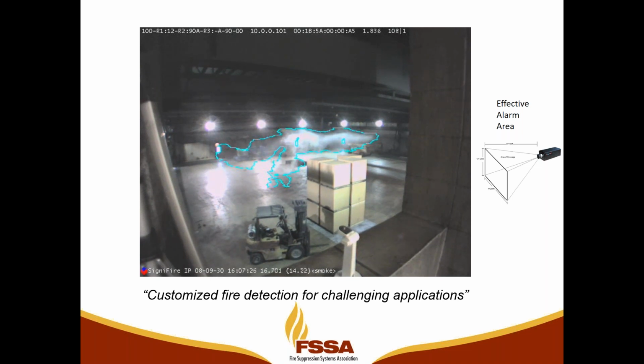Now, if you look at a spot smoke detector, the effective alarm area of that detector is the space between the diode, where the smoke has to reach at the correct obscuration to effect an alarm in the detector. For video analytics, the entire field of view is the effective alarm area. The system can alarm anywhere. Now, if you notice, the smoke did not reach the ceiling. It's obviously stratified, so detectors at the ceiling may not detect the smoke. The smoke may not reach the ceiling, either due to a thermal layer holding the smoke down or not enough energy to propel the smoke to the ceiling. So high ceiling applications, large volume spaces are a great application for video analytics due to the large area of coverage.